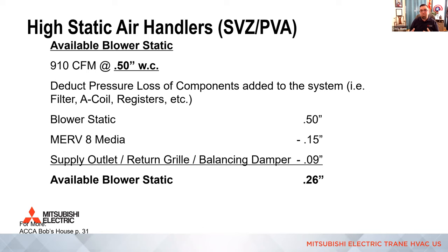Those are large filters. When you put more volume of air through the same size filter, you get a higher pressure loss. So if you remember, the same filter I used with the lower static air handler only had a 0.08 pressure loss. Of course, Andy, great question. We always design around a clean filter. We don't design around a filter that's partly loaded. The ECM motor, if we design around a medium static, should be able to ramp up and overcome a partly loaded filter.